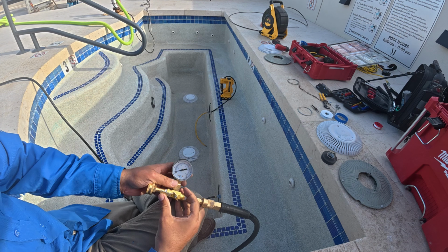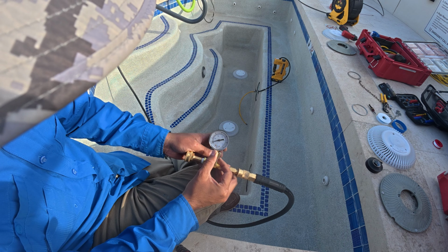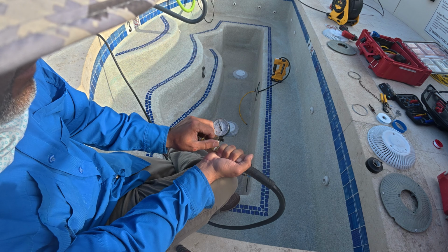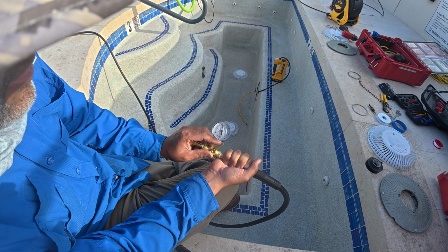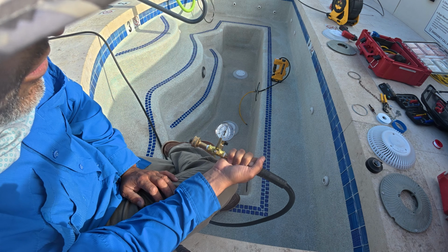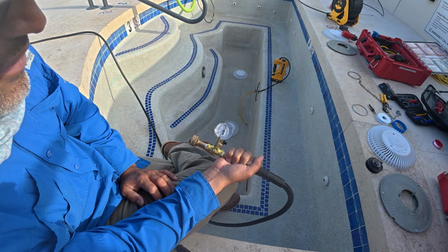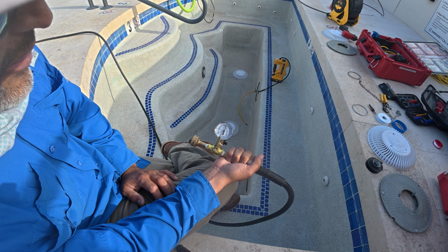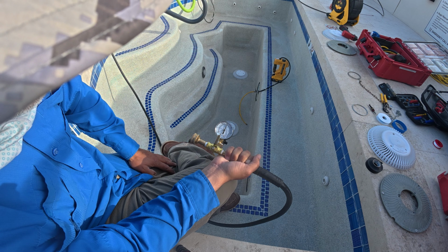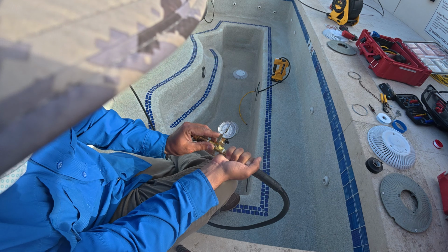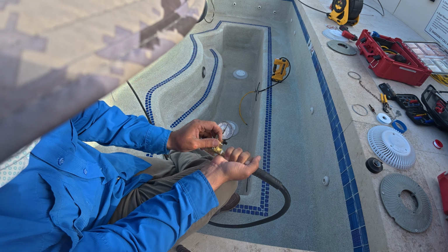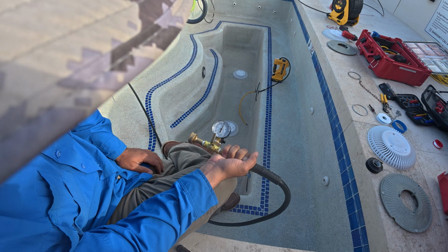So let's go ahead and put some air. We'll just do 15. Slowly. Yeah, look at that. It keeps failing. Okay, it's dropping. And we were called because this is a very small leak, by the way. I think 3 companies were here prior to us. They couldn't find it, so we're going to wait about 5 minutes. Right now it's a little bit past 15 psi. We're just going to put a little bit more love right there. We'll leave it there for 5 minutes and see what it does.